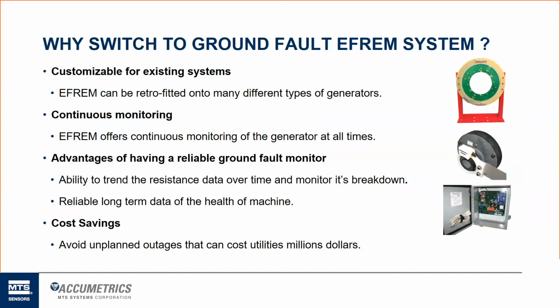Some of the advantages are that ability to trend that data over time, so they can monitor for that breakdown. On their traditional systems, it's literally just a go, no go. You know, that old brush actuator style, they may contact and take a measurement one day and it's fine. The next day you come in, you've got a ground fault. You have no sense of predictability of knowing when that may occur. Do you know if you're at 15K ohms one morning and you're very close to that 10K threshold, and you come in the next day and all of a sudden you've got a ground fault and everybody starts panicking, shut the unit down, and you know, get some repair done. So that's the biggest advantage, is just that ability to monitor it over time.